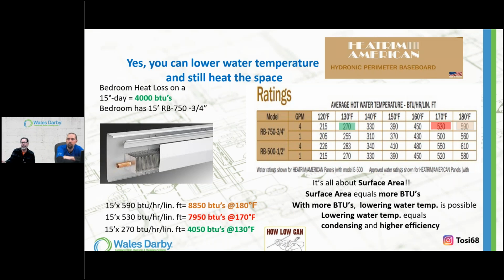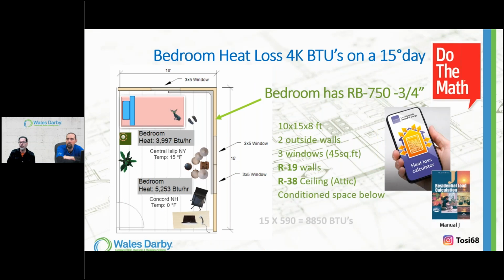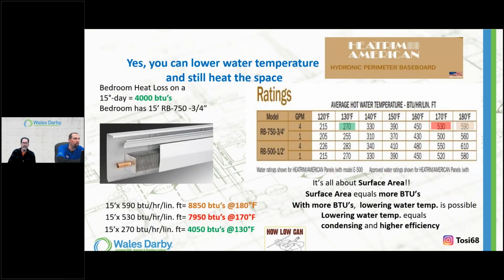So if it was a 0-degree design day, going back to here in Concord, New Hampshire, well, there's 5,253 BTUs. That's what the space requires when it's 0 out. What do I need when it's 30 out? What do I need when it's 25 out? I promise you it's not 5,200 BTUs, all right? So again, using the technology and outdoor weather responsive equipment will monitor and then change its firing rate. But don't think, because the emitter has been baseboard, it's always been 180, that it has to be. I can't do anything other. And that's not the truth, right?